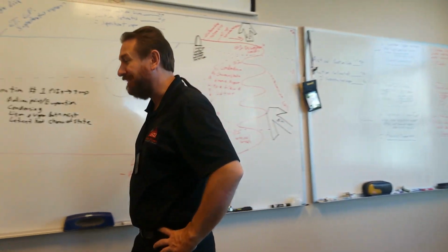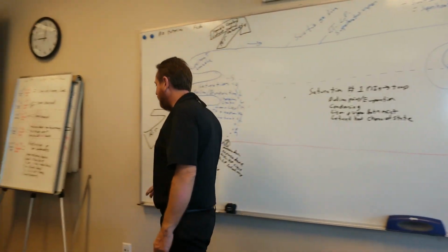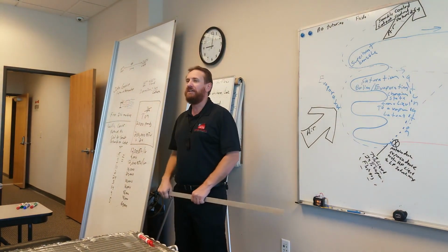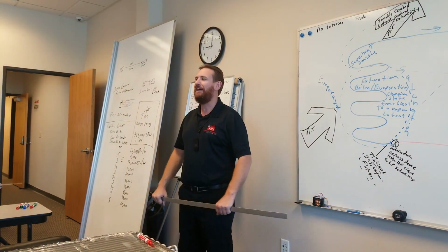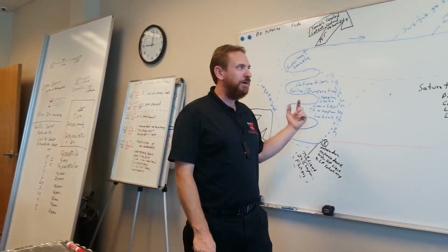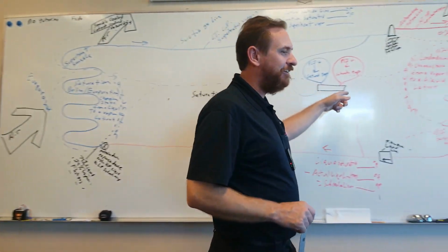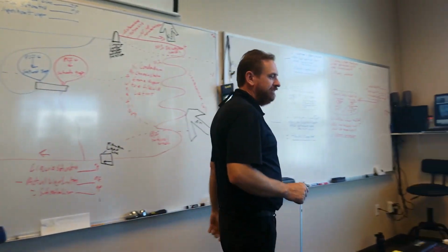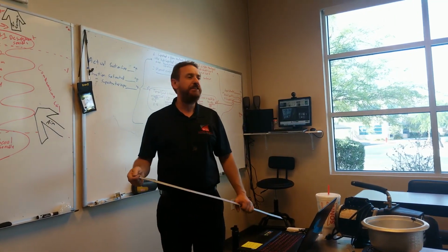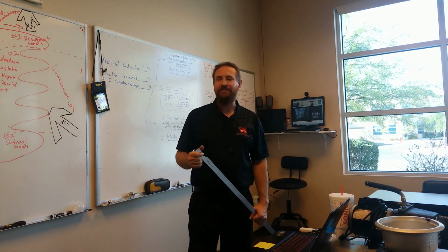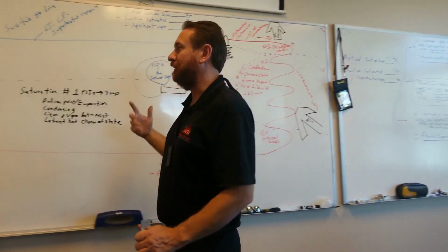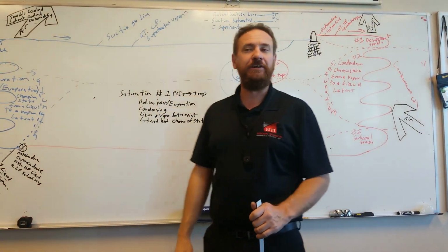Now, that's not a problem here with the dehumidification, but in any other place you go, if you don't dehumidify, it's a big issue. You can have the humidity inside the house way higher than the humidity outside just because you don't dehumidify. So by running that system oversized, it wears it out faster. It also ends up making it uncomfortable. And if you live anywhere else, it causes dehumidification problems. So if you have a unit that's undersized, it'll actually be better because it'll run longer and it'll dehumidify.